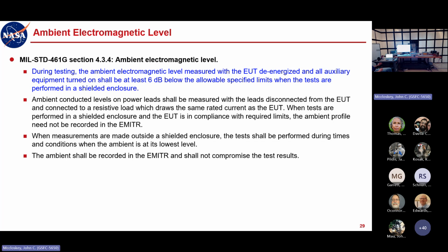ideally you want that noise floor and the RF background to be as low as possible, right? But saying that it's got to be 30 dB below the limit is not very realistic. So I think it's basically a compromise that if you're at least 6 dB below the limit, that minimizes how much it's going to pollute a signal that's just barely meeting the limit. Okay. That makes sense? Does that answer your question?